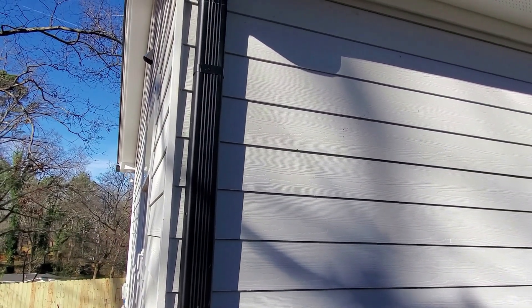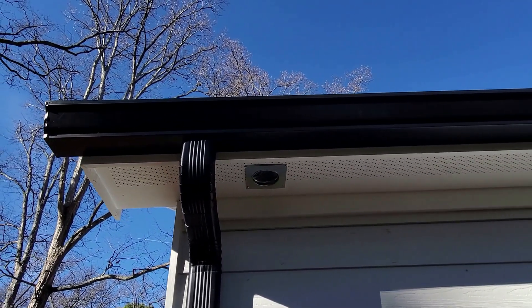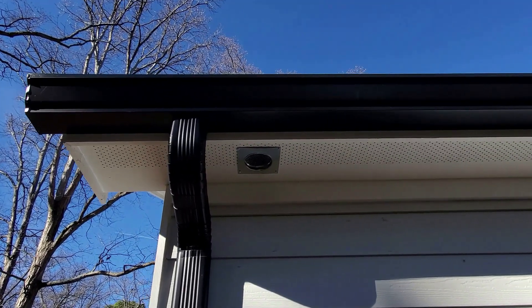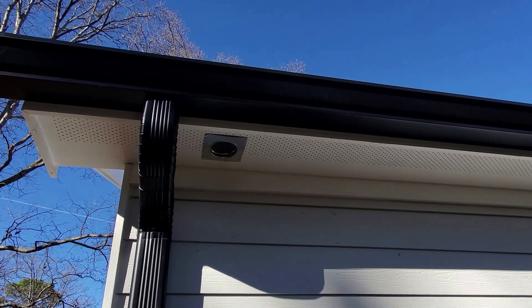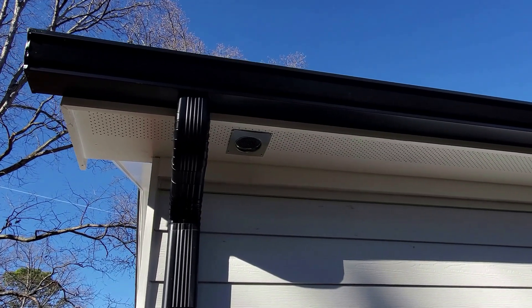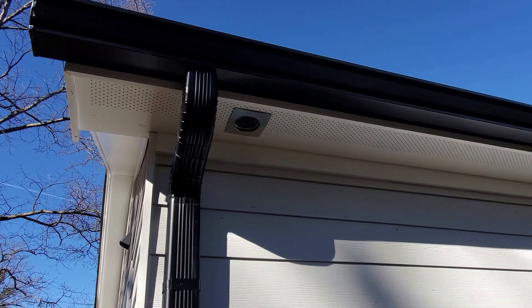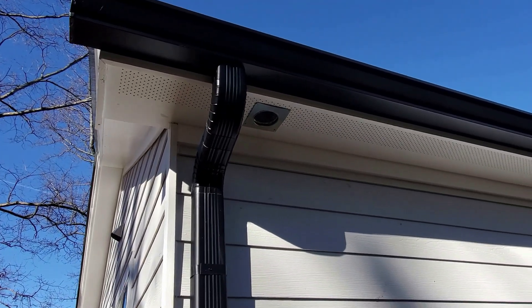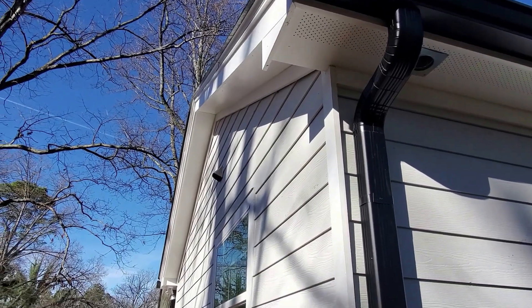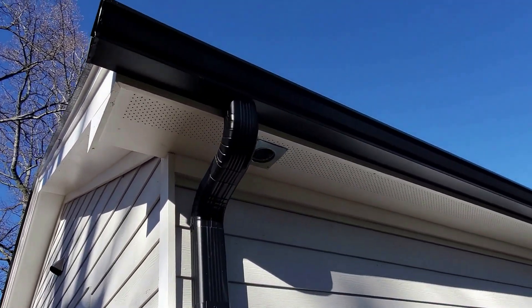Back doing more code violations. I'm here at a new house doing a mechanical final. What you're looking at is a bathroom exhaust going out at a soffit vent. That's definitely a no-no, because that vented soffit is bringing air into the attic, and then you have the bathroom exhaust coming out — that tends to get mixed in with the air going back up into the attic. So you want to either take that out at the side of the house or run it up through the roof.